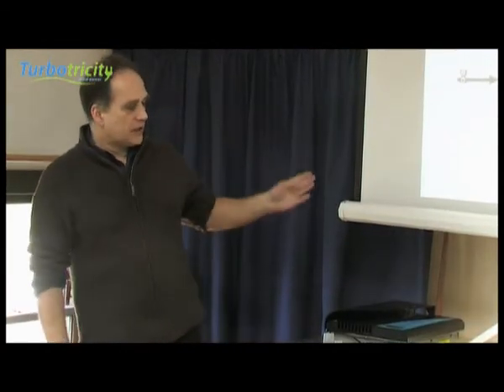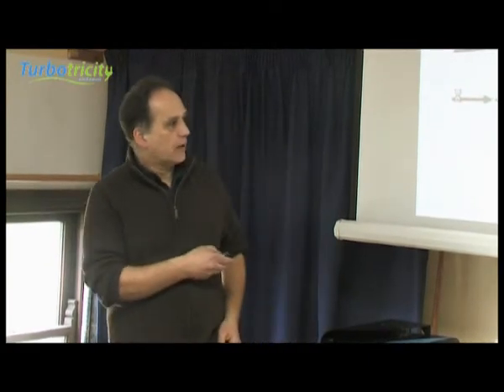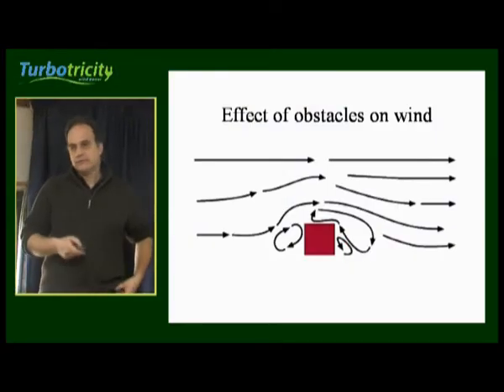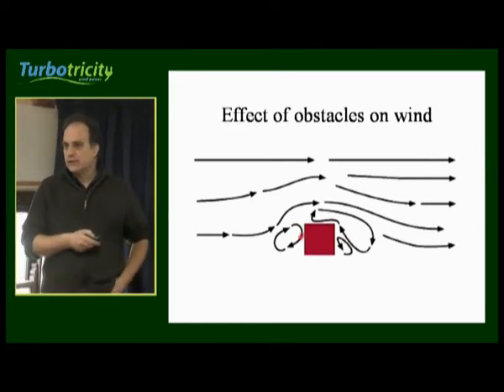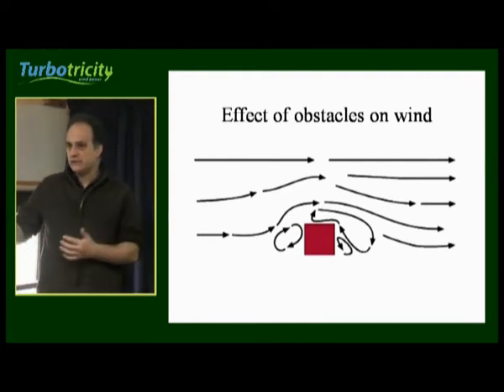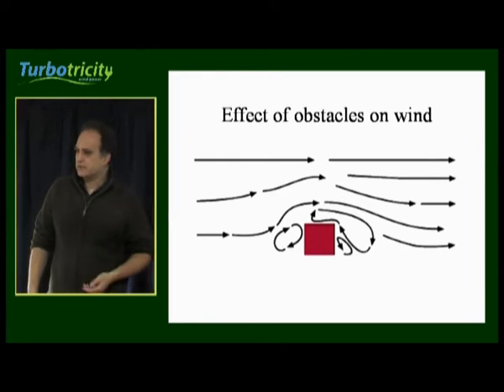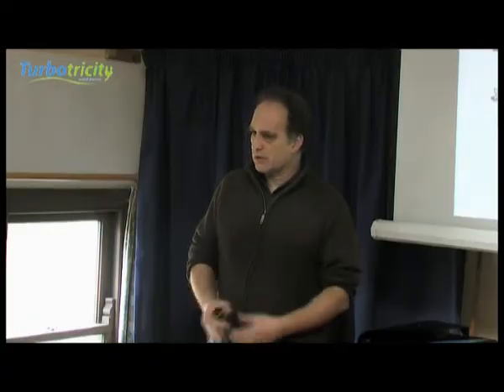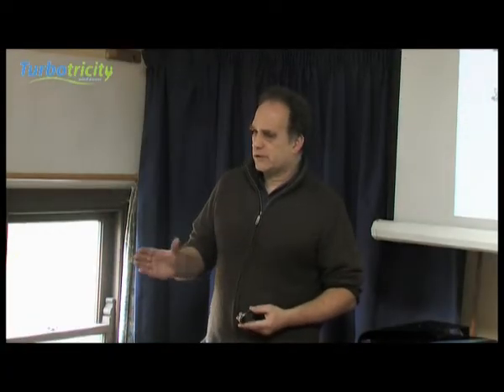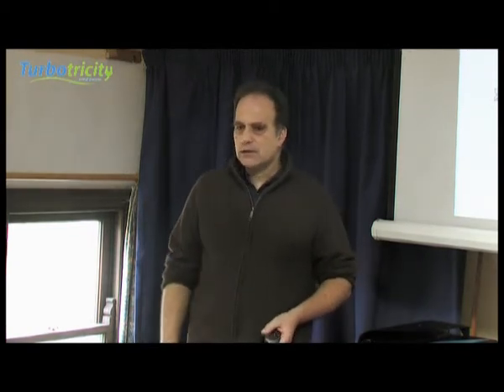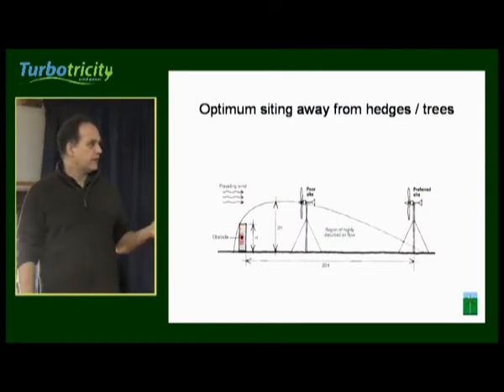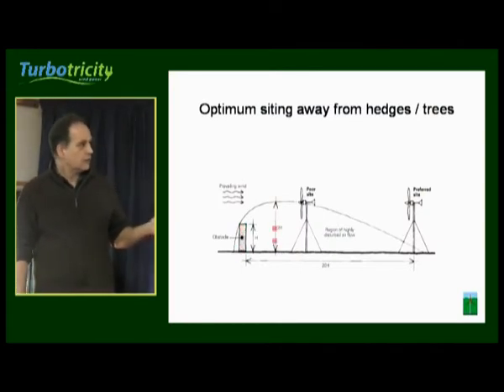If you have a hedge, a ditch, a building, or any other sort of obstacle in the way of the wind, for quite some distance downwind of that you get eddies of wind curling round horizontally and vertically — this sort of turbulent gusting wind. You still stand in a spot in the field and think it's windy, but unknown to you the wind is turbulent, mixed with high and low pressure, and fluttering in direction all the time. Ideally, if you have a hedge say five metres high, your turbine needs to be at twice that height and 20 times that distance away.